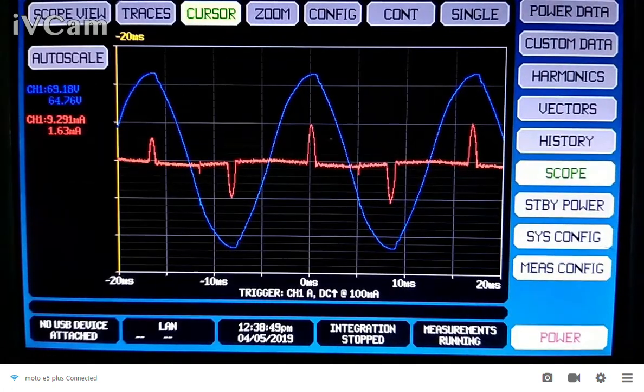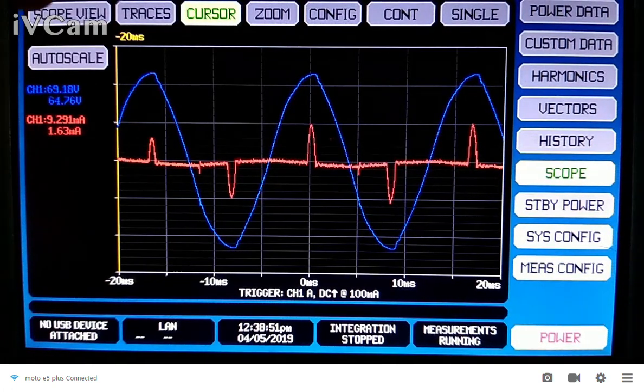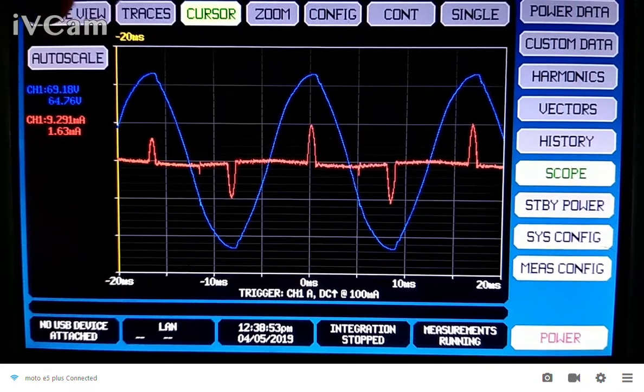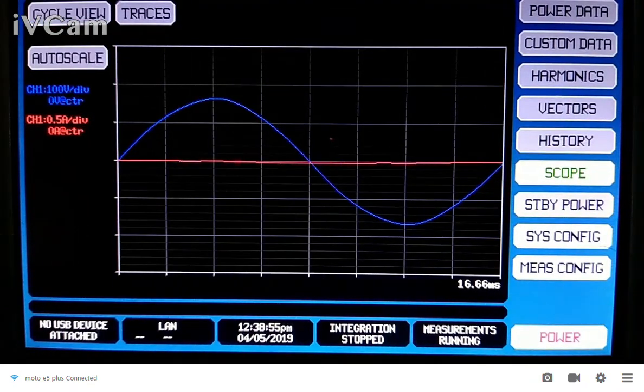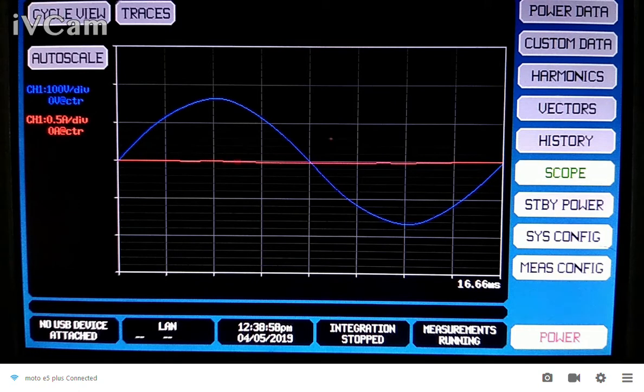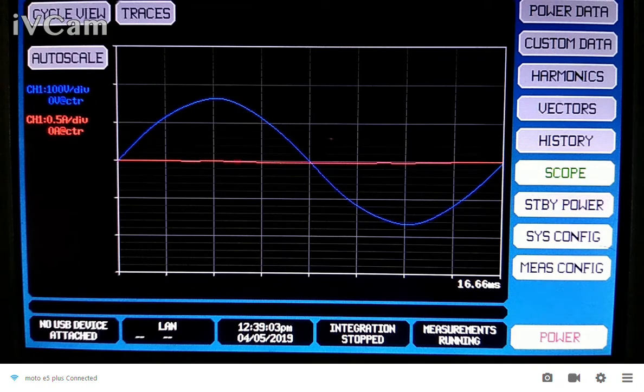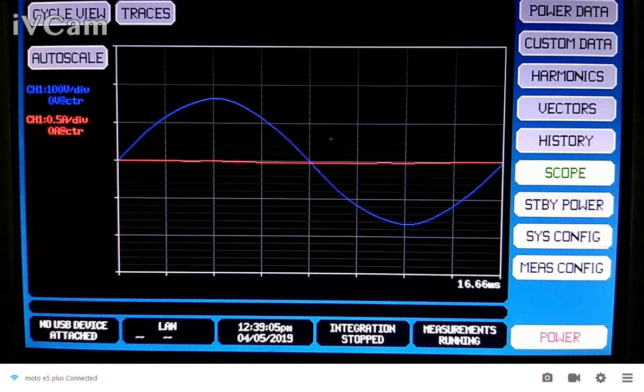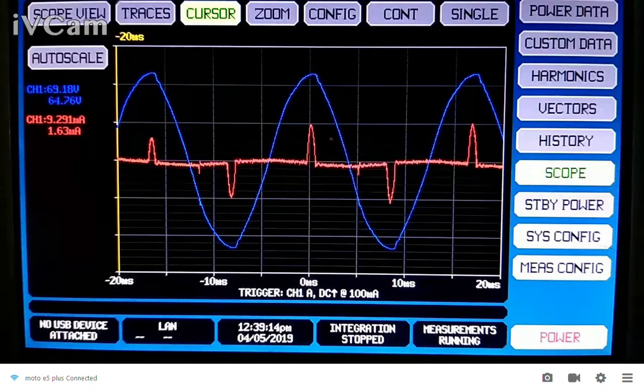So, the scope can be used in a couple of different modes. One is called a cycle view, and in a cycle view, it automatically sets the time base and auto scale up so that you get one cycle displayed at a time. But for what we're going to do, we want to measure inrush current. We're going to come on over and tell it to go into the oscilloscope mode.